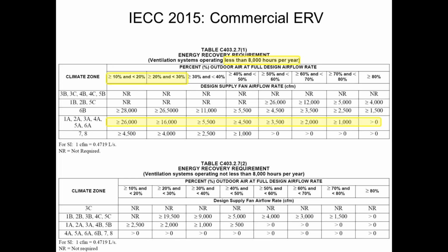So we're climate zone 5A, and it used to be for us on the previous version of the code, we only had the 30% and larger tables. So if I had a 5500 CFM supply fan with 30% outside air, I would have had to do an ERV. If I had less than 30% outside air, there was no requirements at all. Now I have a column for 20% and a column for 10% outside air, although granted it does apply to fairly large fan systems. So those two columns are new for 10 and 20%.